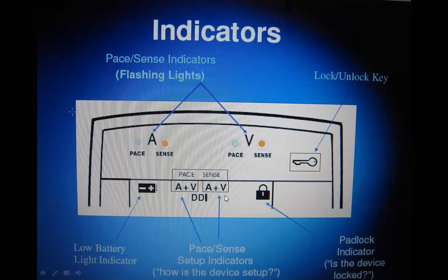Also, we can adjust to any mode you want. If you notice on the machine we posted on the group, there are 4 knobs. The fourth one can help us adjust the mode setting we want. The temporary pacemaker can also be adjusted to a mode setting. If you want VVI, AAI, DDD, whatever mode you want. But one thing you notice is that it will not give you the 4th alphabet.